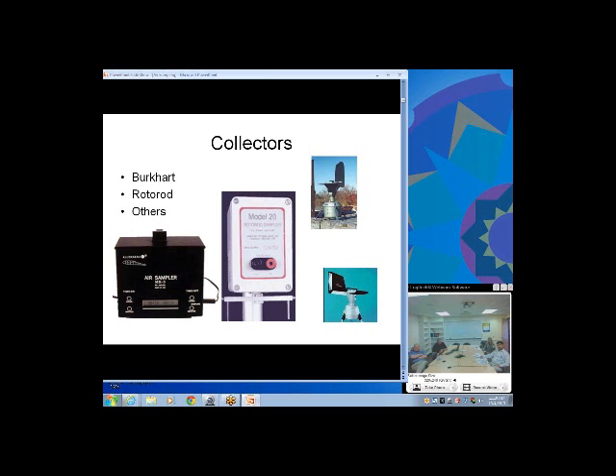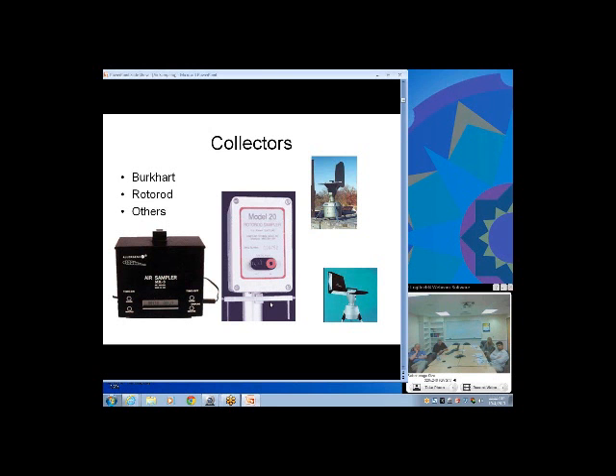We have three different types of collectors. First, outdoor spore trap type collectors with a vacuum device and a small slit that spores and pollen are pulled through, impacting on a grease-coated piece of plastic or sometimes a grease-coated slide that moves with time. Second, a rotor rod type device set for time intervals — the rods at the bottom spin and you calculate how many pollen stick to the grease-coated lucite rod.